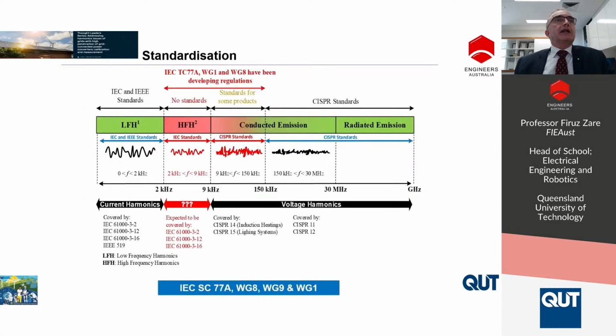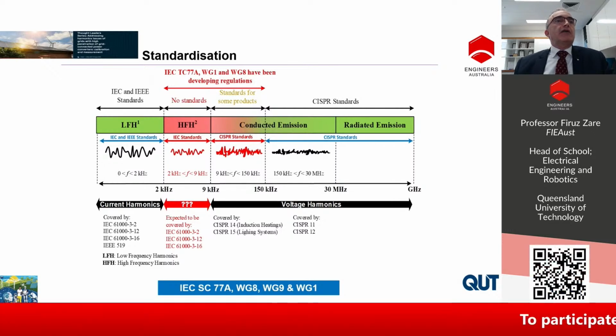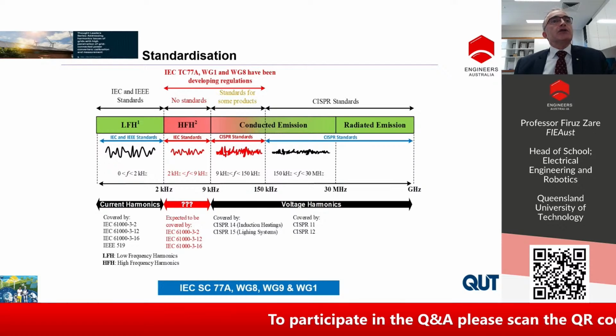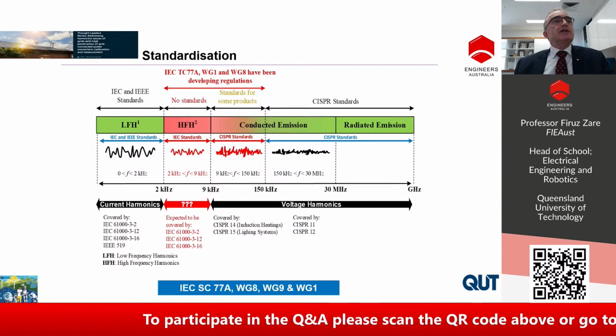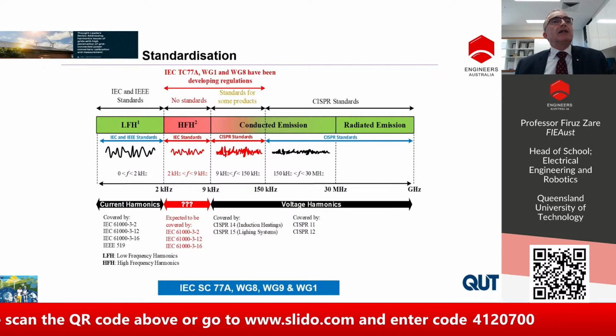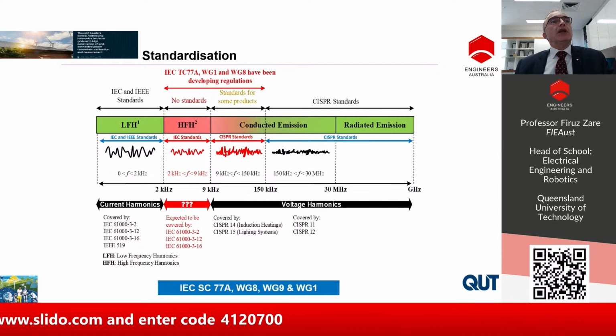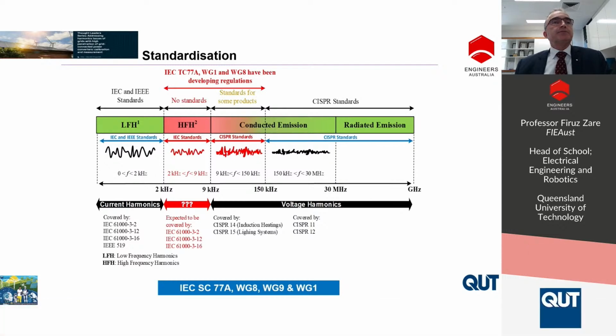So there are different standards in the network to make sure that the quality of the network can be controlled. When we are talking about harmonics below 2 kilohertz, we have several standards and regulations that we can work on. IEC 61000-3-16 is one of the new standards that I'm the task force leader for, and this is specifically for grid-connected renewable energy systems. But the other standards for harmonics are for low power or high power.